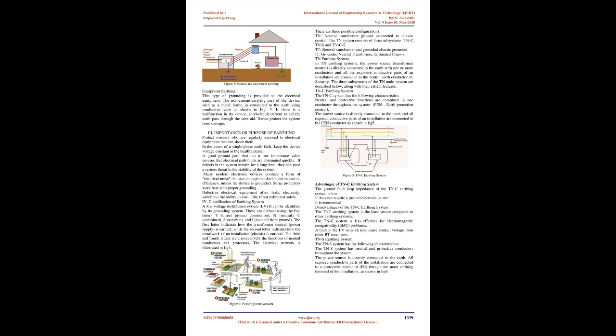TN-C earthing system. The TN-C system has the following characteristics: neutral and protective functions are combined in one conductor throughout the system. PEN, earth protection neutral. The power source is directly connected to the earth and all exposed conductive parts of an installation are connected to the PEN conductor as shown in Fig. 5.